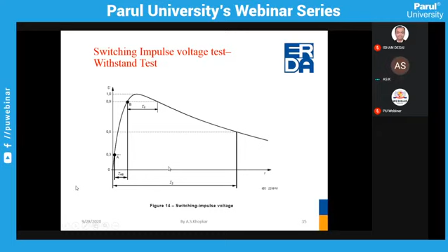This test is almost similar to the lightning impulse. The method is almost the same. Only thing here, the time duration is different. Otherwise, the waveform looks the same, but the time scale is different. Here the 50 microsecond, it was 10 microsecond. And these are the parameters which we'll have to maintain during the switching impulse. The wave shape is 250 microsecond by 2500 microsecond. The meaning is that front time should be 250 microsecond and tail time is 2500 microsecond.